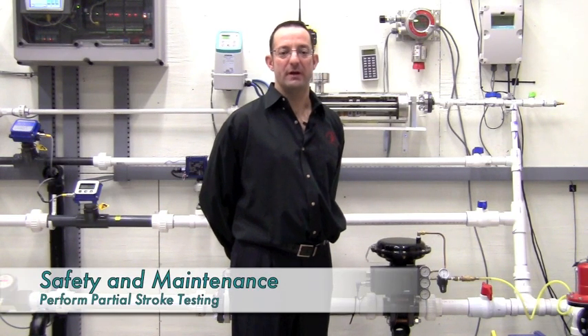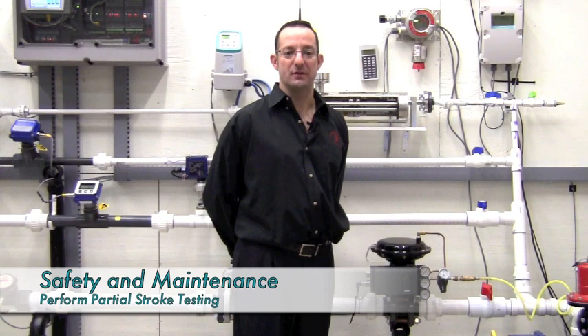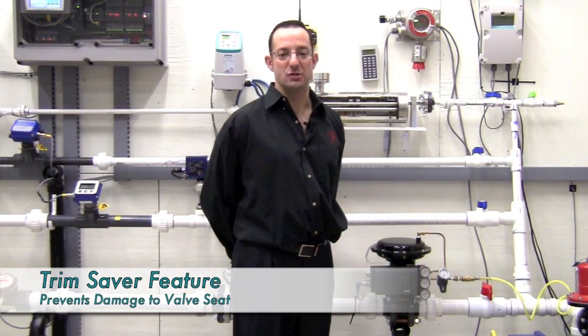For safety related applications, the PS2 can perform periodic partial stroke testing to ensure that the valve is ready to act when your safety system tells it to. For high pressure drops across the valve, you can activate the trim saver feature, which prevents wire drawing and damage to trim on valves as they approach the closed position.